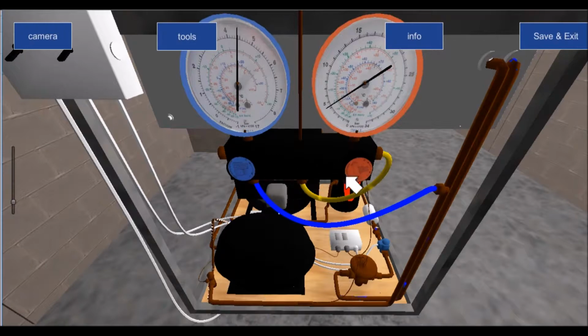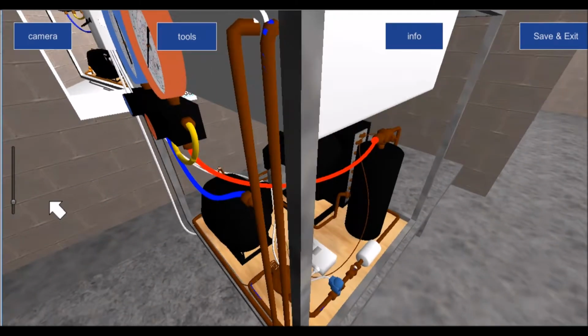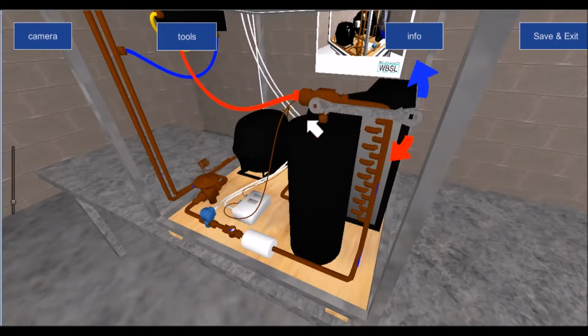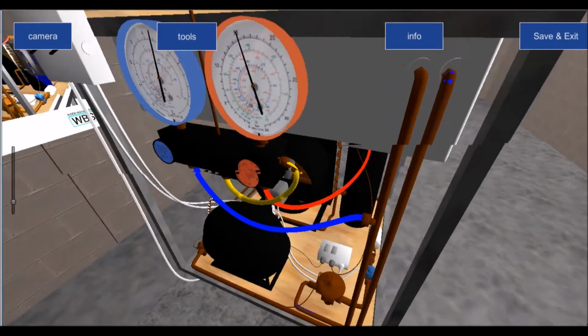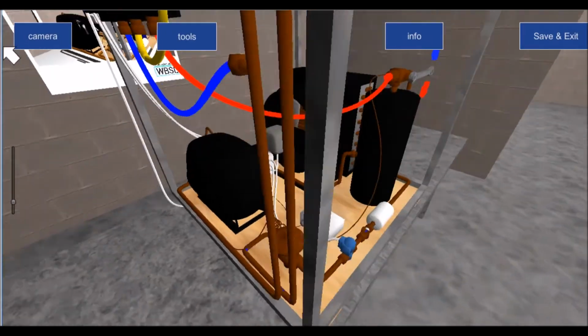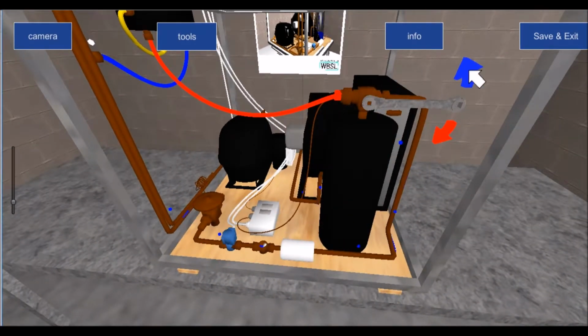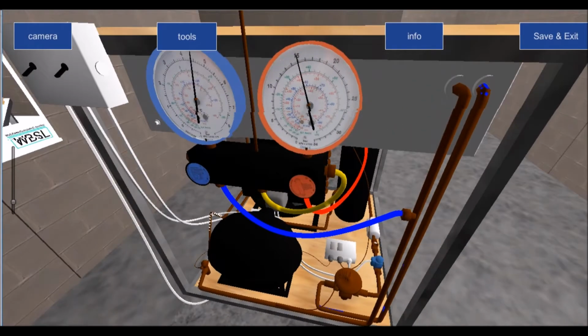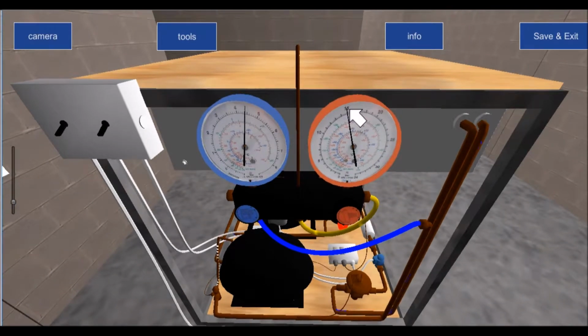Now, the reason why we need to make sure these two valves are closed or shut off is because as soon as I put my valve ratchet onto this job here, if it allows me to do it. Yeah, from there now. Okay, so what I did was I fitted the valve ratchet on. I cracked the valve ratchet by literally just, you can see, a quarter of a turn there. And then once I cracked the valve ratchet, what you see happening here is on the high side of the gauge you see 15 bar. On the low side of the gauge you still see the 4.5 bar that's there, or just over 4 bar, 4.4 bar.